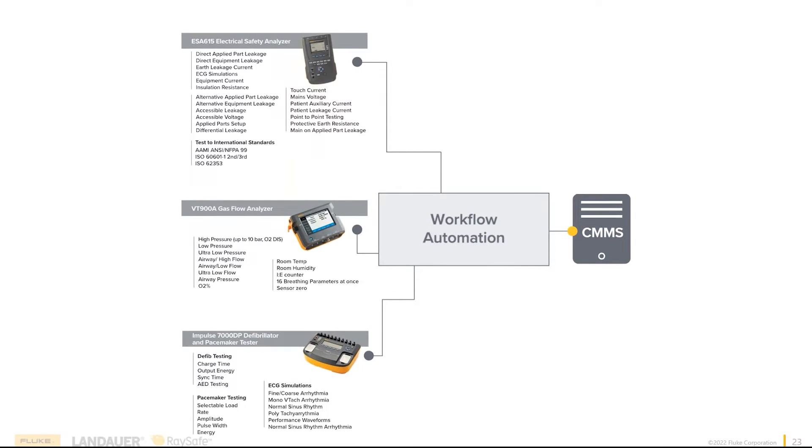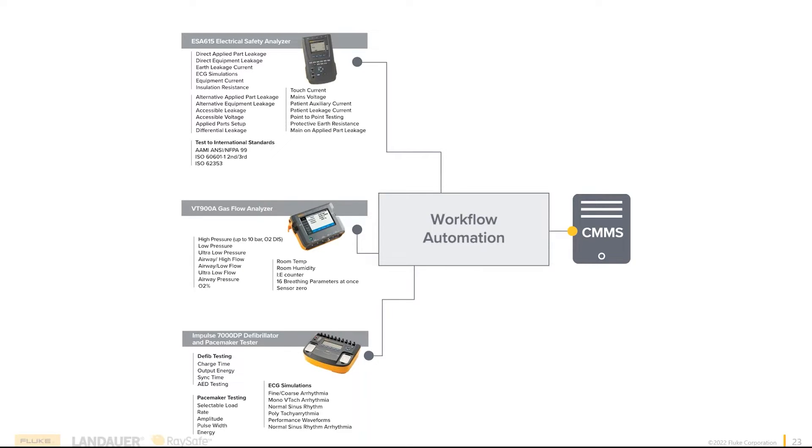But it's more than that because it's also our electrical safety analyzers and all the tests that come with it, and the different standards. If you're in-house hospital Biomed following your PM procedures, you're following NFPA 99, and it has the load for that. With our ESAs, maybe you're doing a factory upgrade, and you notice it calls out the 62353 standard. Do you have the appropriate loads for that?